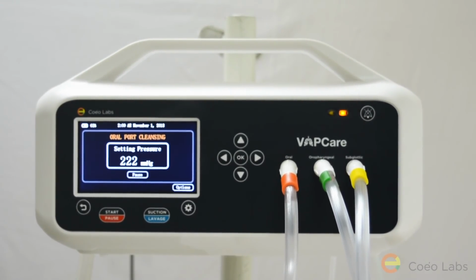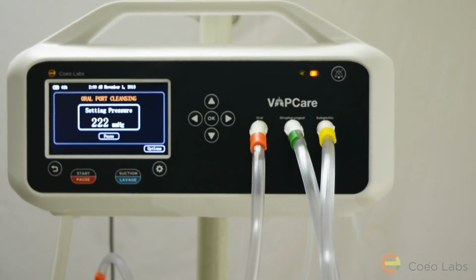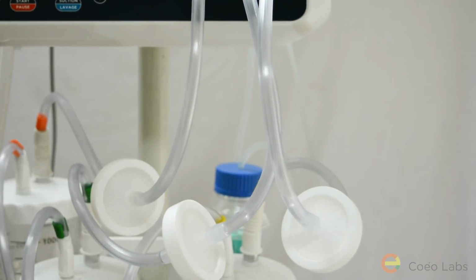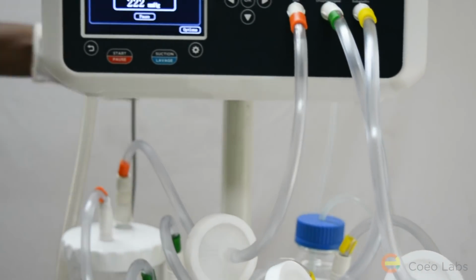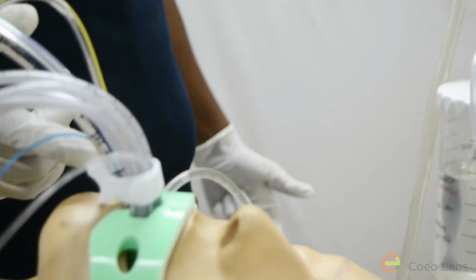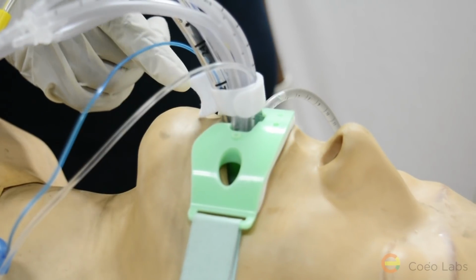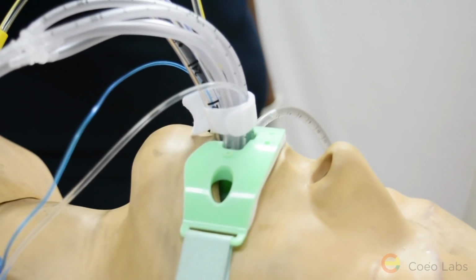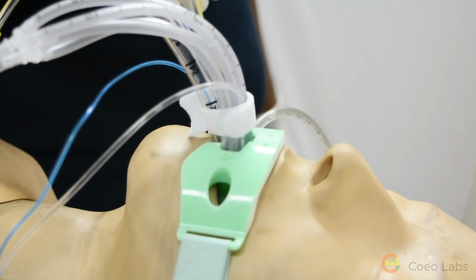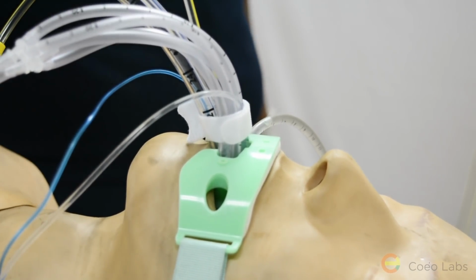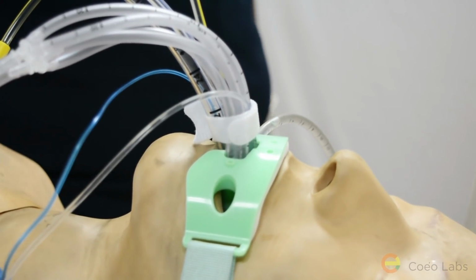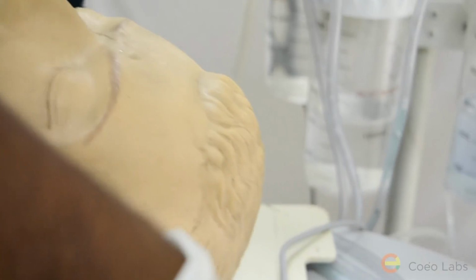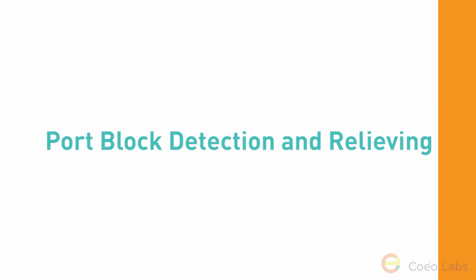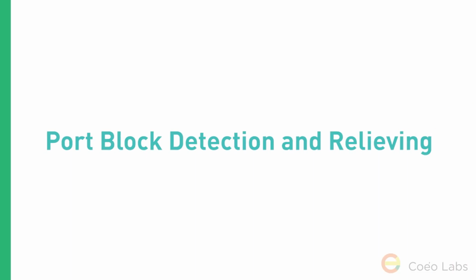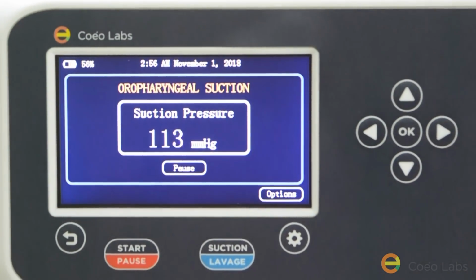a mandatory suction cycle. Now you can see the pressure is set to 222, and the lavage is being sprinkled, and then the lavage fluid stays in the patient's oral cavity for around 15 seconds. Then the device starts suctioning simultaneously from all three different locations. Now you can see the suction is sucking out from the subglottic region presently. The device has port block detection and relieving feature.